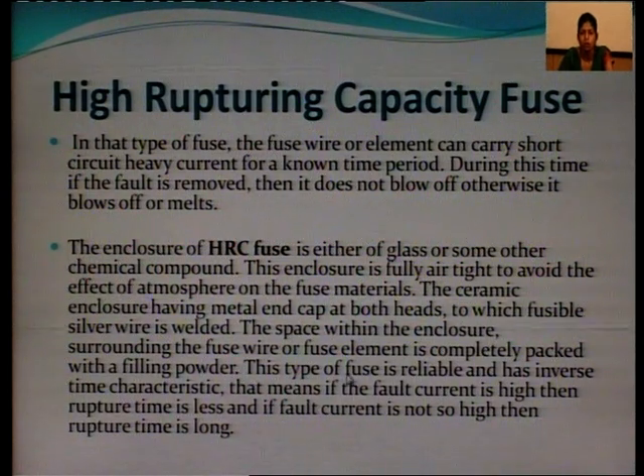This type of fuse is reliable and has inverse time characteristics. That means if the fault current is high, then the rupture time is less, and if the fault current is not so high, then the rupturing time is long. This kind of behavior is called inverse time characteristics.